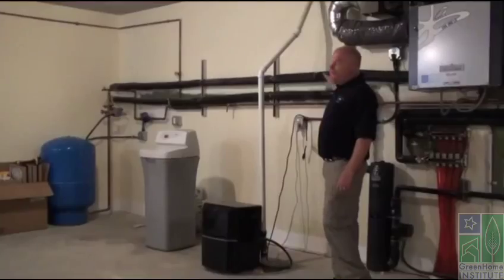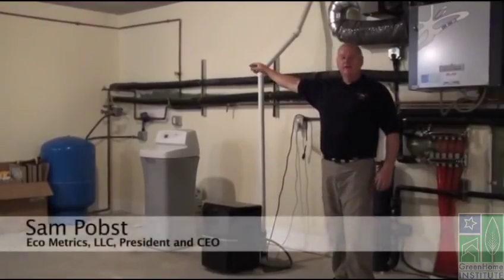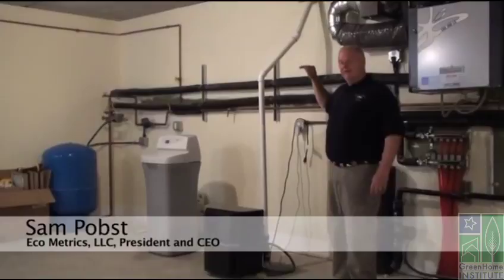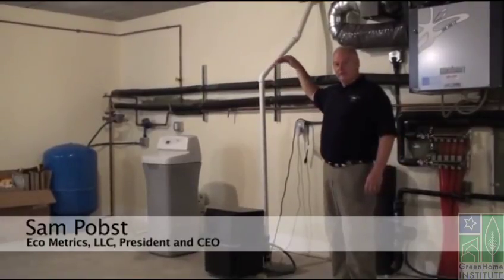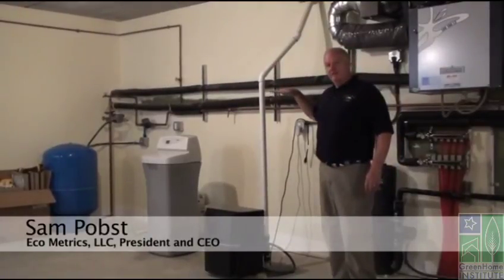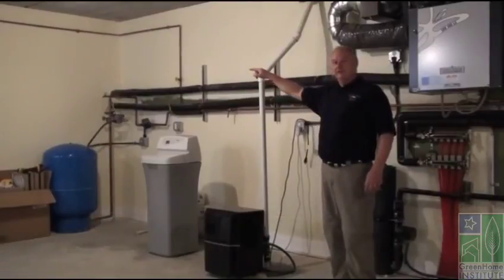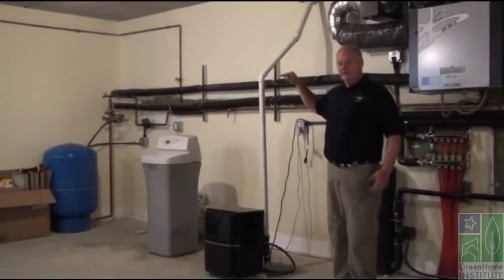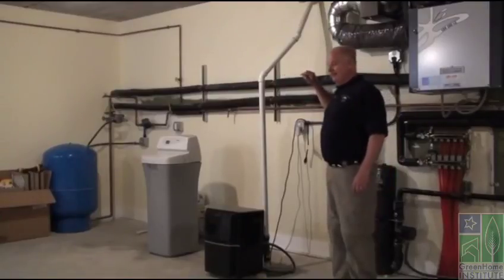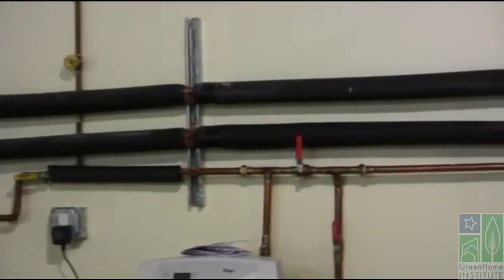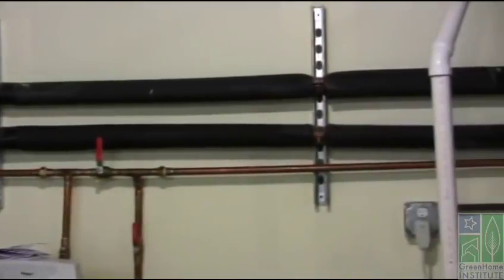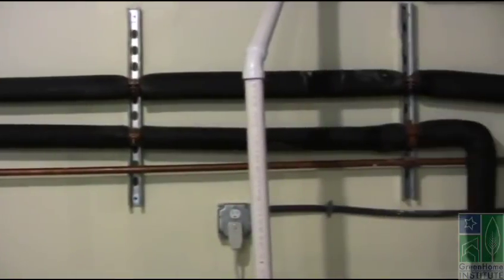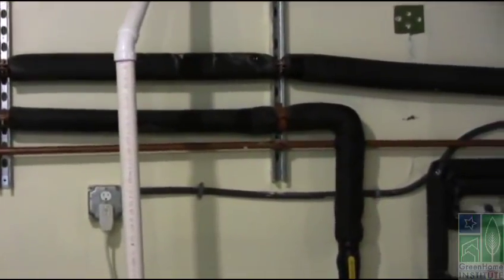Pipes go out into the front yard through that wall. And we had a horizontal drilling rig which will drill pipes into the ground horizontally. And we have 2 loops that go out into the yard that are about 250 feet long. And they're filled with glycol, so they won't freeze. They're about 25 feet deep, so there's not much chance of them freezing anyway.